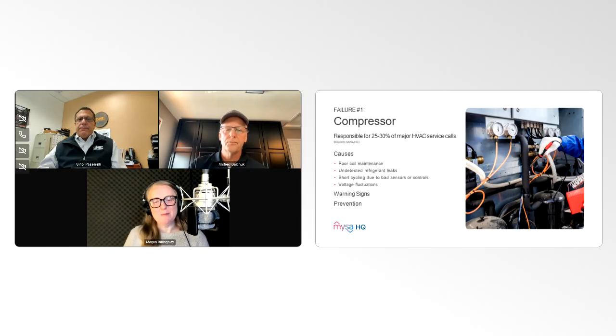Excellent. Thank you so much. So let's move on now to fan failures, which can take comfort down levels quickly. Andrew, what's a clear sign that a fan or blower motor isn't working correctly? For sure. So, if a blower is failing, obviously it's going to be where you simply have little or no airflow coming from the supply air vents itself. It's very obvious at that point.